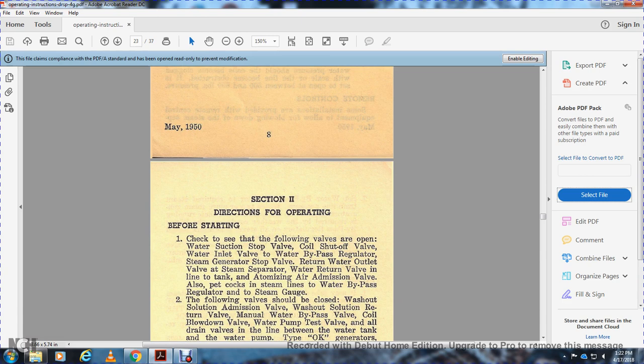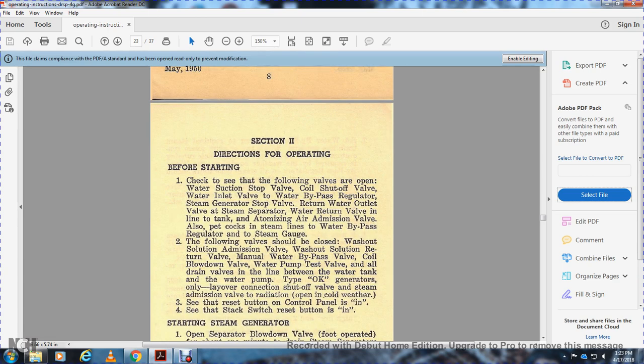Section 2, directions for operation. Before starting, check to see that the following valves are open: the water suction stop valve, the coil shutoff valve, the water inlet valve, the water bypass regulator, the steam generator stop valve, the return water outlet valve, the steam generator separator water return valve in line, the tank atomizing air admission valve, also the petcock, the steam line, the water bypass regulator, and the steam gauge. The following valves should be closed: the washout solution admission valve, the washout solution return valve, the manual water bypass valve, the coil blowdown valve, the water pump test valve, all the drain valves in the line between the water tank and the water pump, the layover connection, and the steam admission shutoff valve, with the radiation open in cold weather.